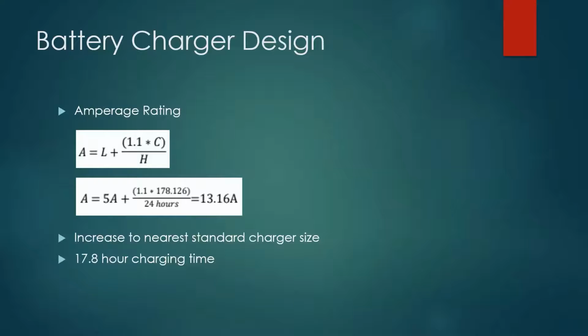For our battery charger design, we used this equation here to find the amperage rating of the battery charger. Using the numbers given, we were able to find a battery charger size of 13.16 amps. However, this is not a standard battery charger size, so we had to increase it to the next closest standard size, which was 16 amps. Plugging this number into the time section of the equation, we found that our charging time was 17.8 hours.